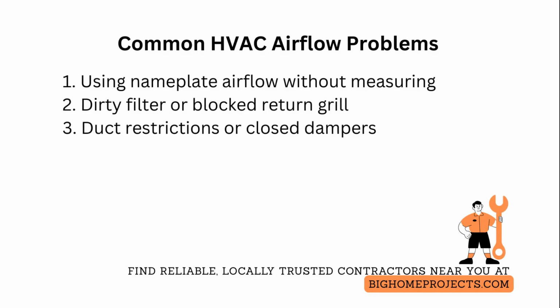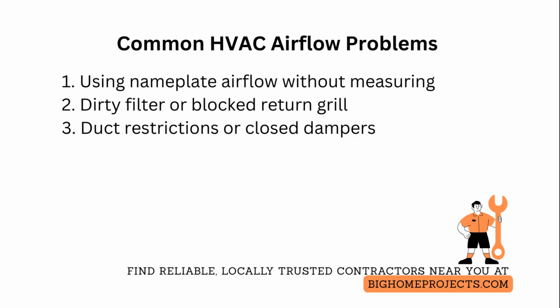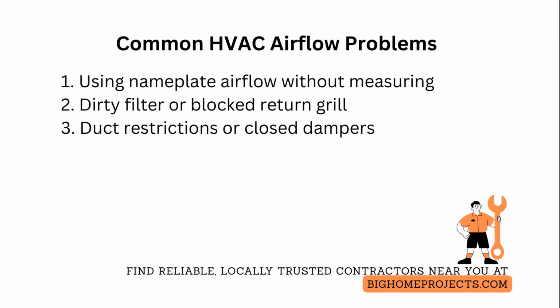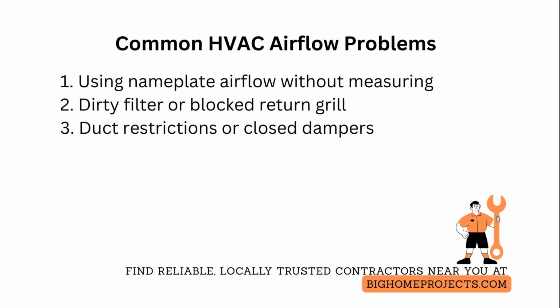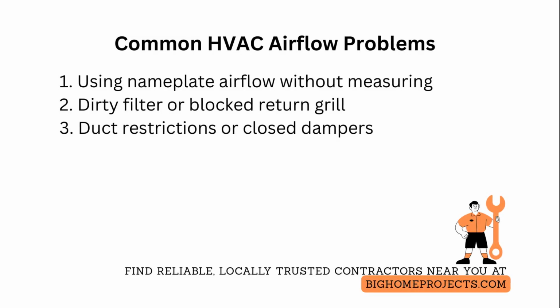The third common problem is ignoring duct restrictions from crushed flex, undersized boots, or closed dampers that increase static pressure and reduce airflow. Locate restrictions with a systematic walkthrough, temporarily bypass suspected runs to isolate the drop, and then repair or resize ducts, reconfigure dampers, or add return capacity as needed.